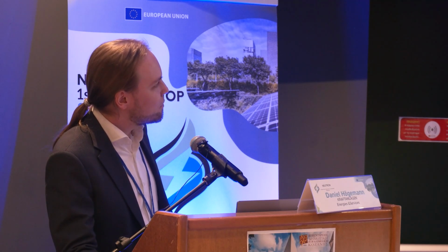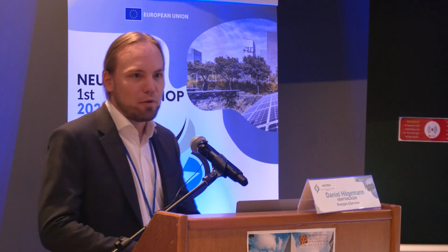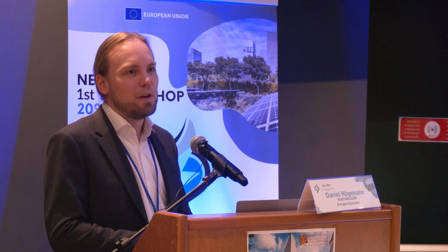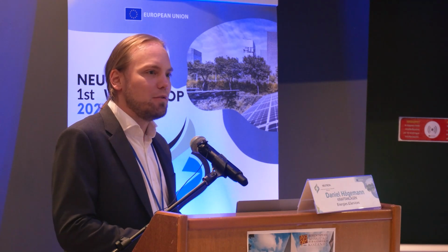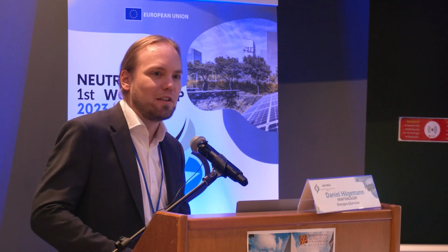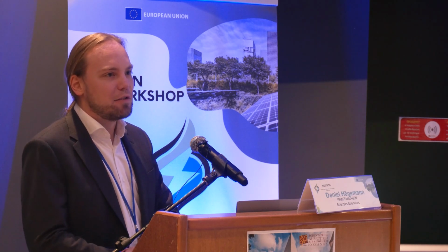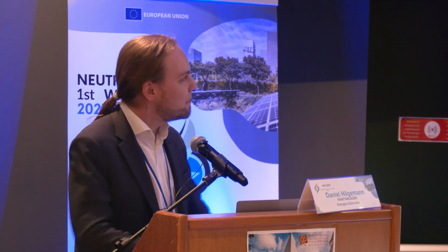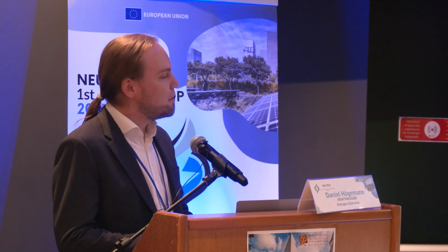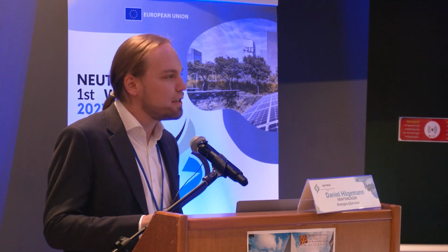What the system does is, when we have renewable electricity available, or what can also be used is, for example, surplus electricity from a grid. We've already heard that in Greece there is already in many regions the problem that renewable electricity cannot be generated because the electricity grid is basically full, so they have to turn down. So the system could also use this electricity, which would otherwise not be generated, and convert it to high temperature heat. The electric heater is then heating up a flow of ambient air to temperatures up to 1000 degrees Celsius.